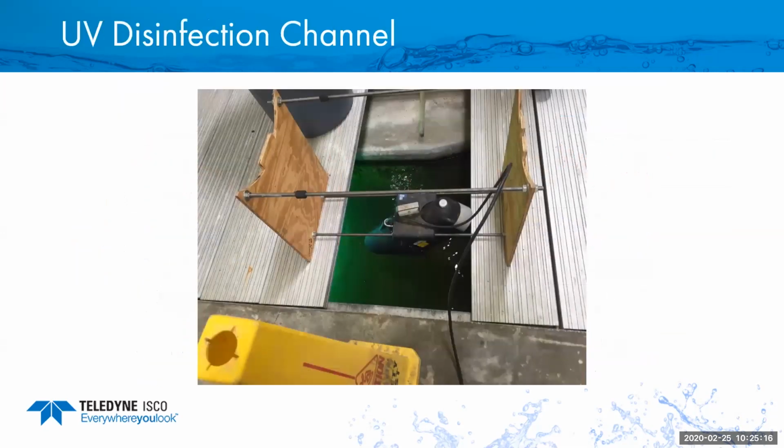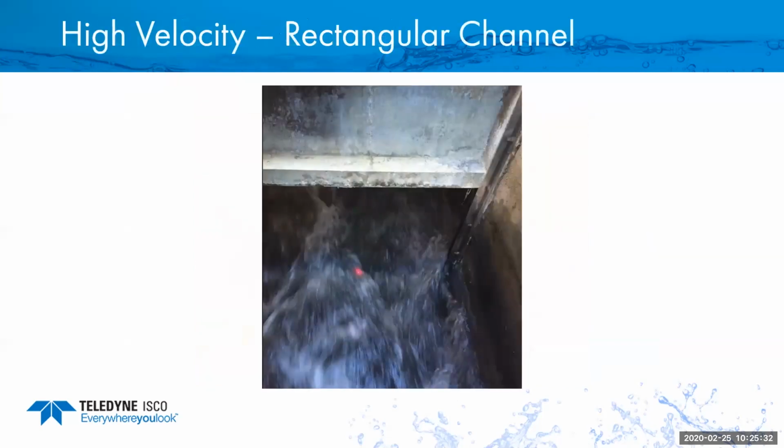good thing for them. This is one where I just did a temporary test to find out how clean of water we could read. This is the wastewater plant in Lincoln, Nebraska. It's very, very clean water coming out of there. And the laser was able to actually measure that very accurately and quite well.